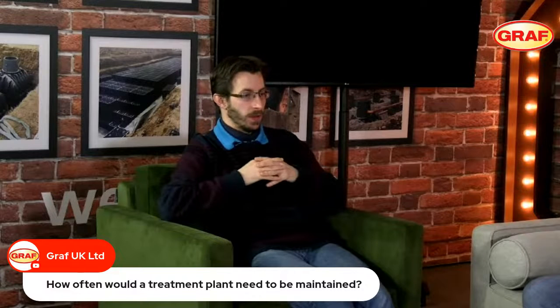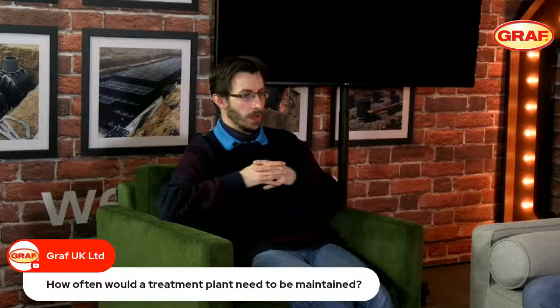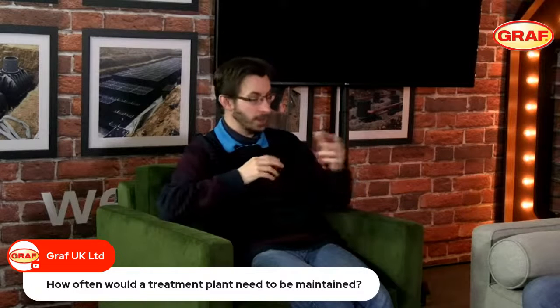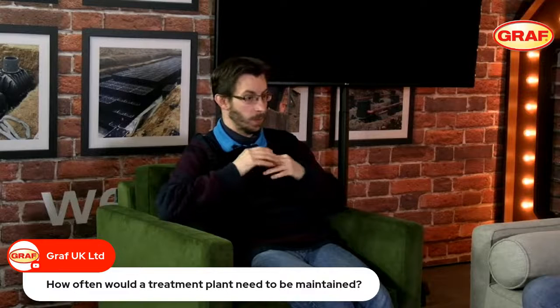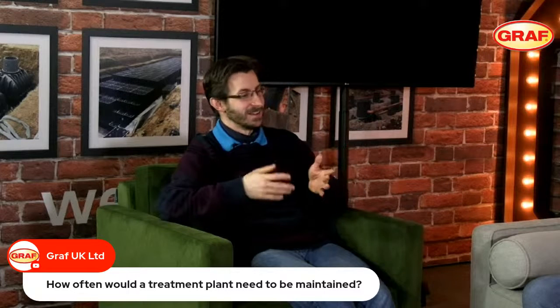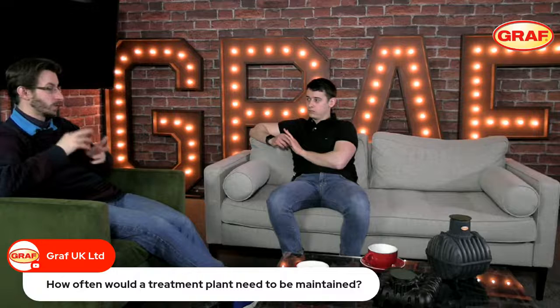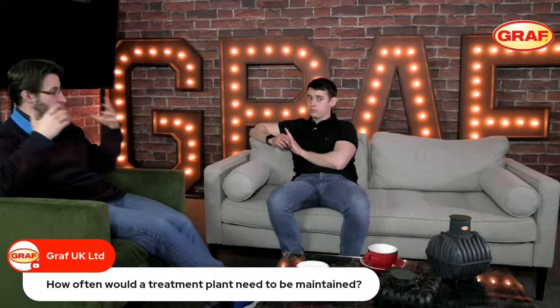So I think it's quite important to remember, though, that if you have got a servicing set up on a system, it's important to do the system servicing first before you then have the tank emptied. It's basically to get an understanding of how well the treatment plant is performing. We need to have, of course, sludge within the tank. So if you have the tank emptied prior to going to do a system service, of course, we haven't got a fully working treatment plant. So it's good to stagger the two, just to ensure that we're getting the best understanding of how well the treatment plant is performing.